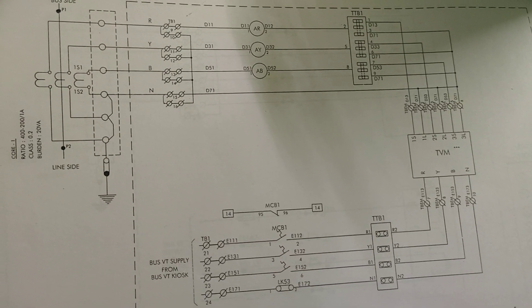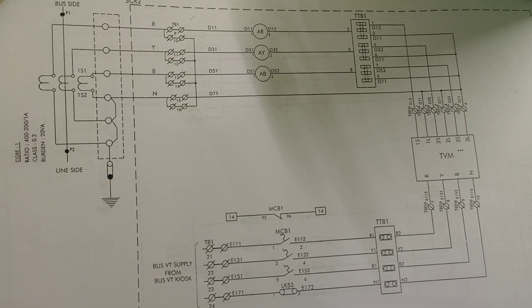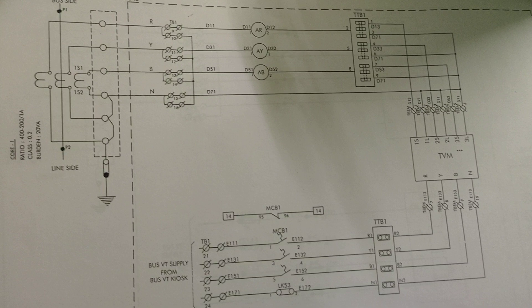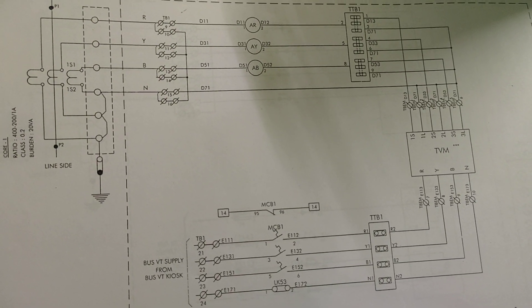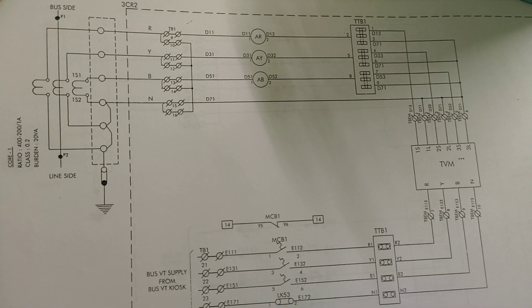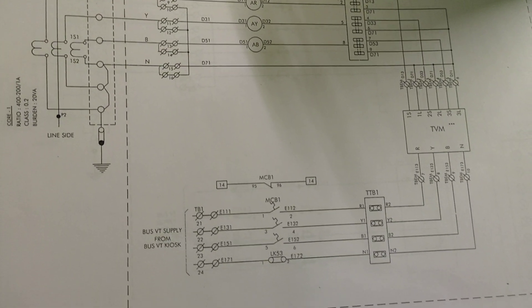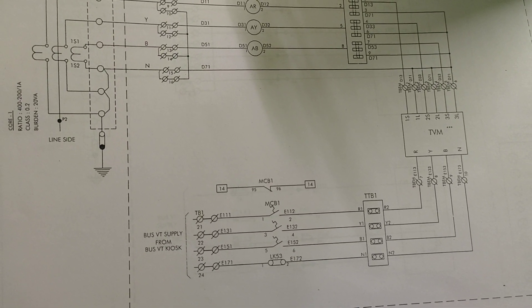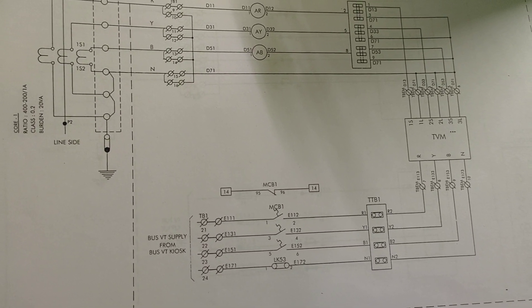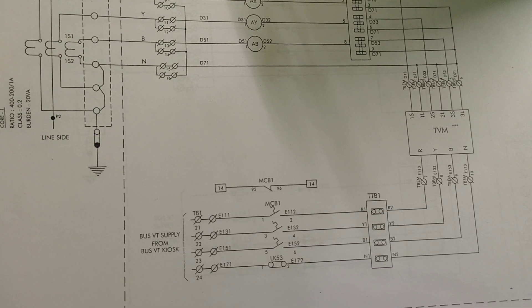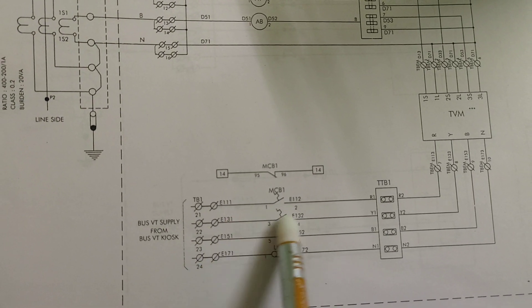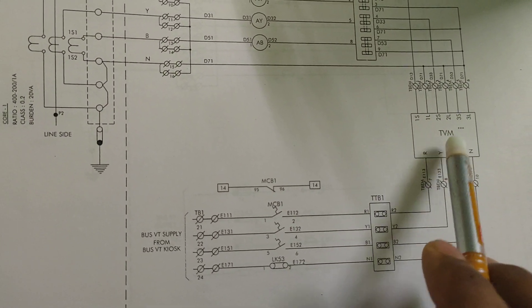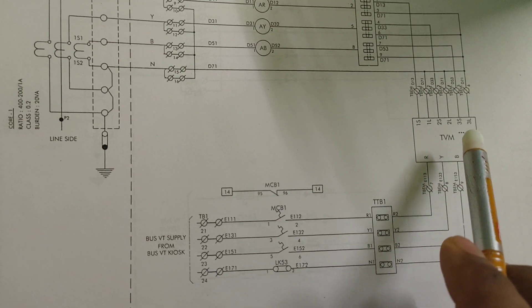At all voltage levels, the first core is the metering core. Its accuracy class varies — 0.2 or 0.5 — and here 0.2 accuracy class is used. From the VT side, for all voltage levels (11, 33, 132, 220, 400, 765kV), the VT connection feeds the energy meter for energy auditing and supervision — to measure how much energy is consumed from a particular line.